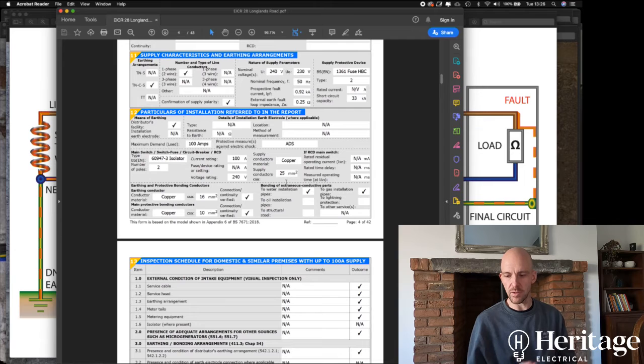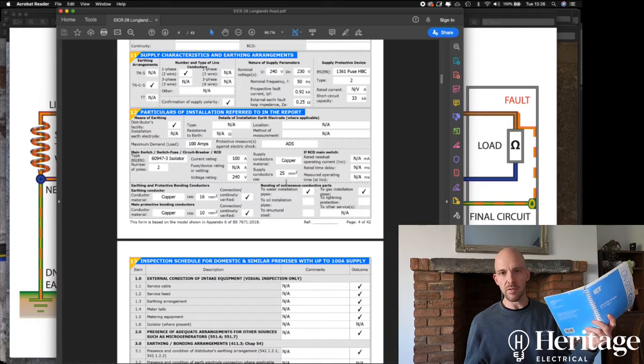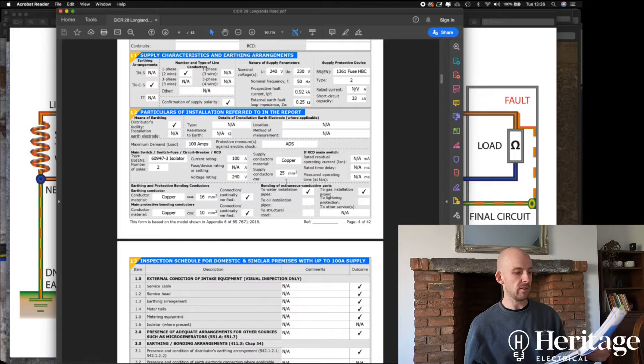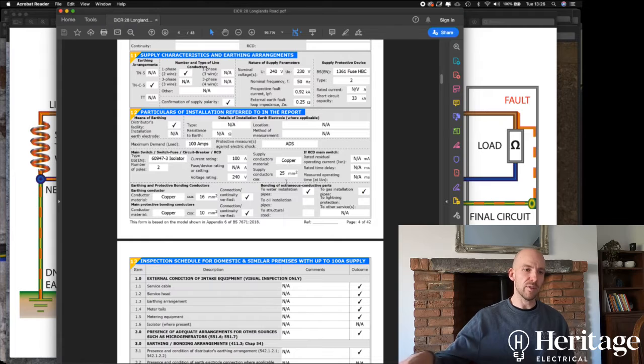Now we check this because, again, just going back to our on-site guide, and these numbers are in the main wiring regs as well. If we look at a 25 millimeters squared single core cable, which is what it is, that can carry over 100 amps. And so the cable is protected by the main cutout fuse if it's rated at 100 amps. The thicker the cable, the more current can flow in the cable without the cable overheating. The skinnier the cable, the less current can flow in that before the cable starts to get warm and potentially overheat.